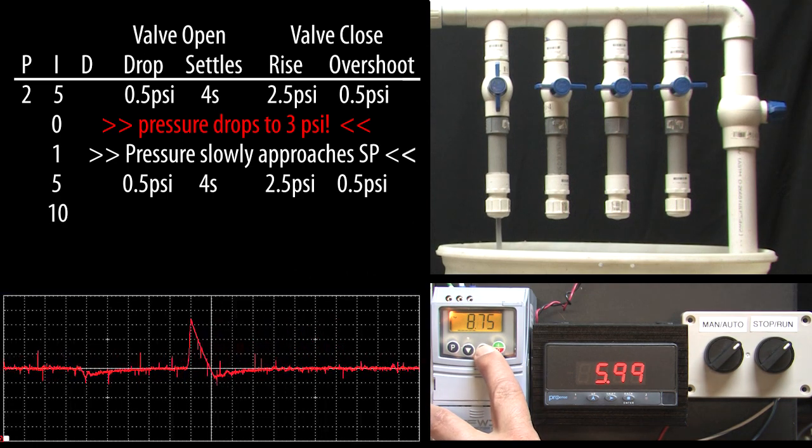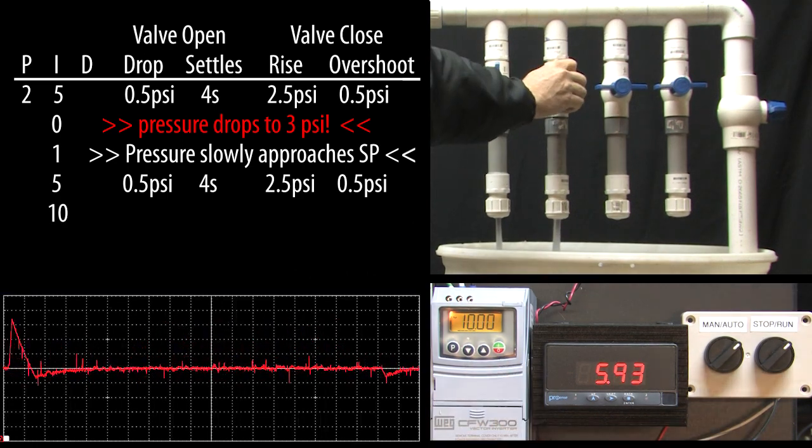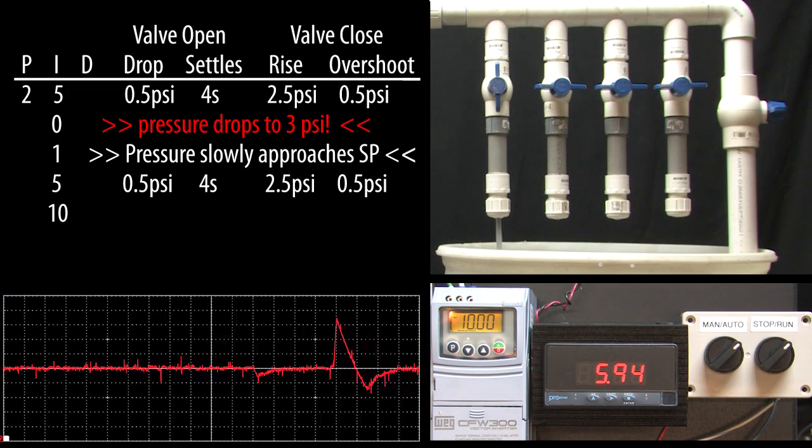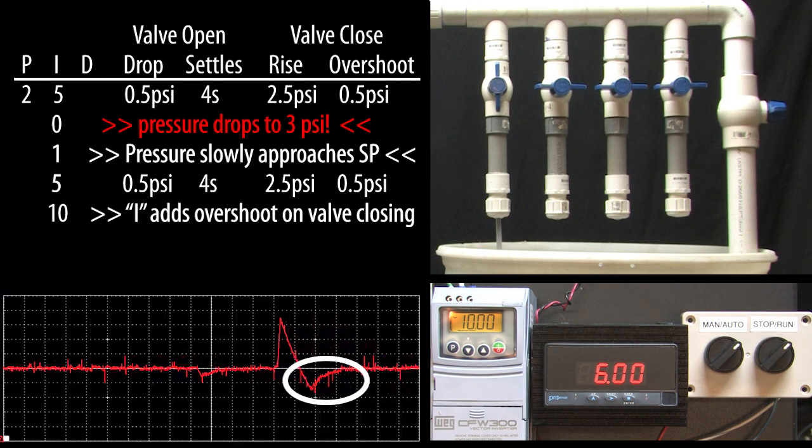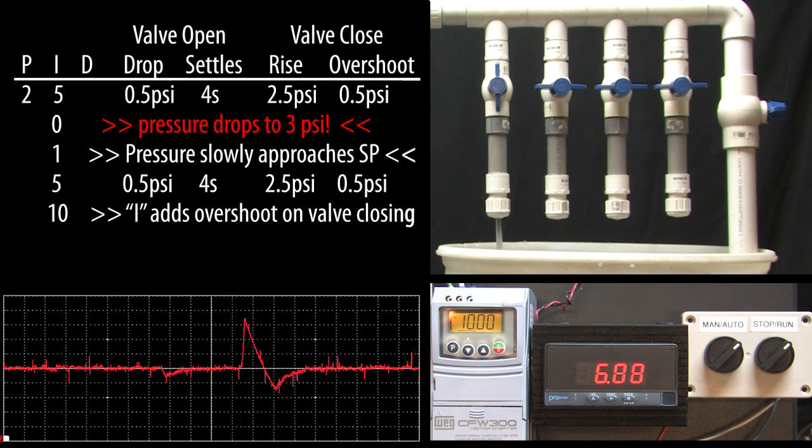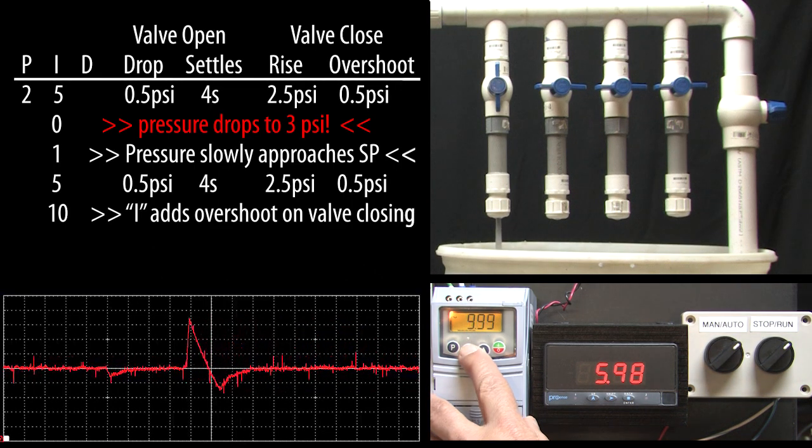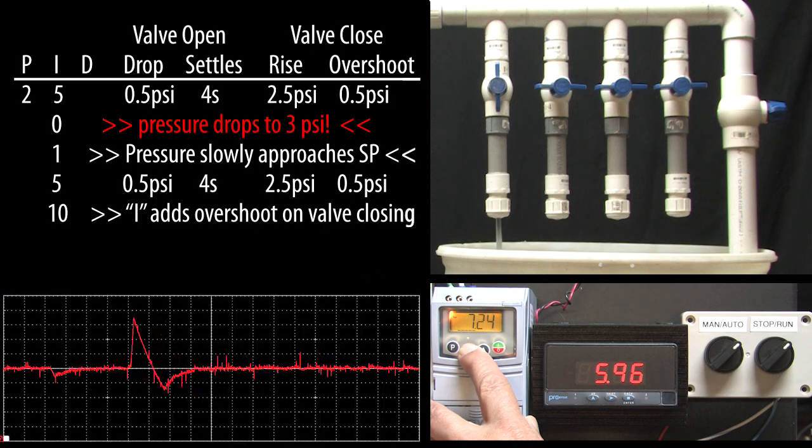OK, let's double I to 10 and open and close the valves. Ah look, the I term seems to be the one that's impacting the overshoot on the valve closing. And since we were doubling it every time we doubled P, it kept getting worse. So that begs the question, could we reduce I and increase P to get a faster response with a smaller overshoot?